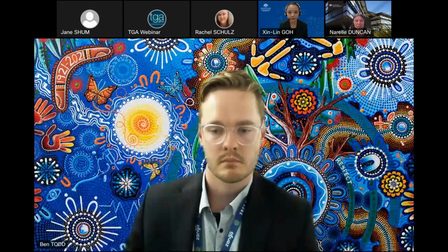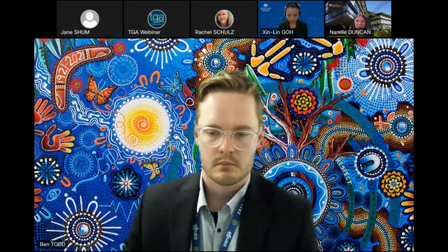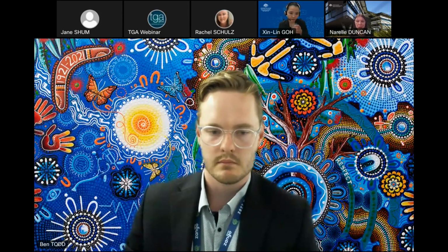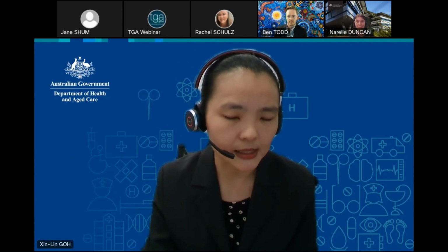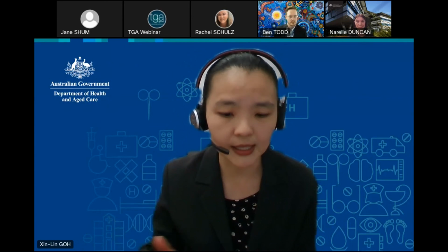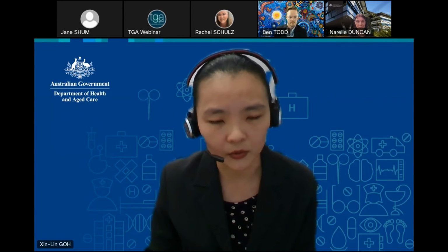Great, thank you. Our next question is, are products registered on the ARTG using other kinds of conformity assessment, for example, MD-SAP, out of scope of the EU MDR transition requirements? If products are supported by MD-SAP or other non-European certification, they aren't affected by the EU MDR transition as such. Having said that, very similar rules will apply. So if their MD-SAP certification expires, for instance, it's legislated that they will have to notify us within 60 days. So those same rules will apply.